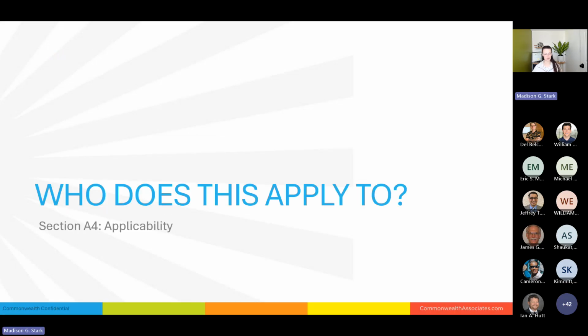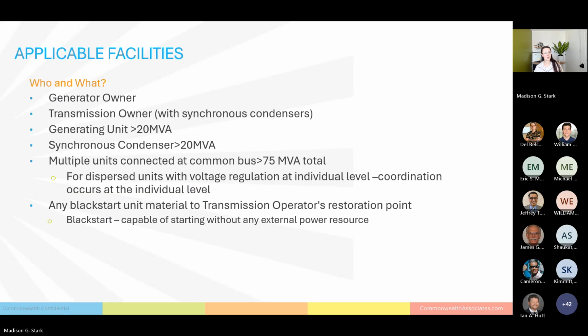Who does this apply to? Great question. This applies to two general groups of people, generator owners and transmission owners. For a unit to fall under PRC 19 requirements, it has to be over 20 MVA capacity. That's 20 MVA, the apparent power, not 20 megawatts, which is a little bit of a different rating. Same thing for synchronous condensers. Any synchronous condenser over 20 MVA falls into this category.